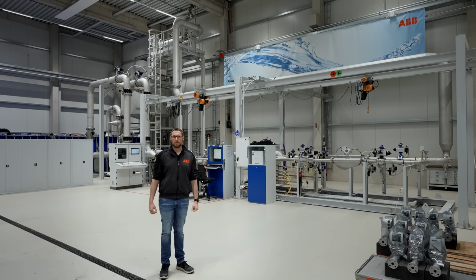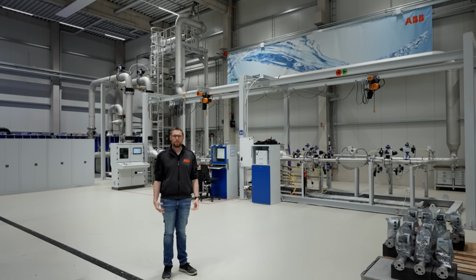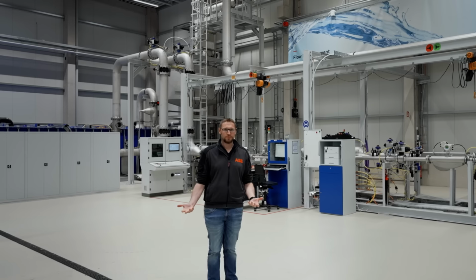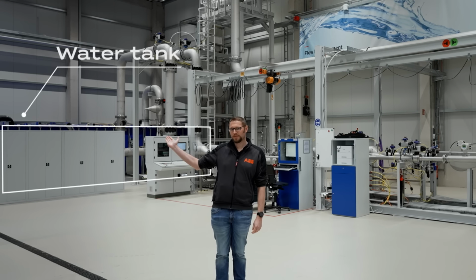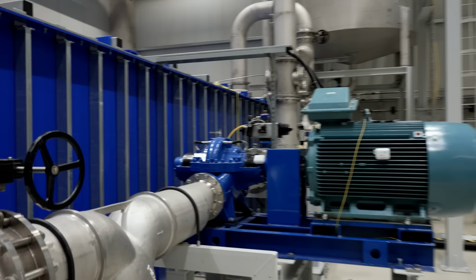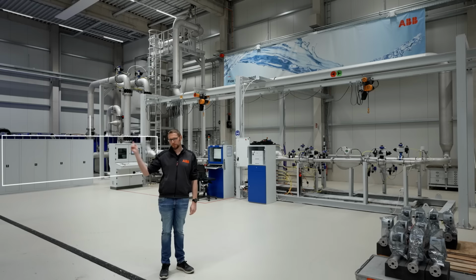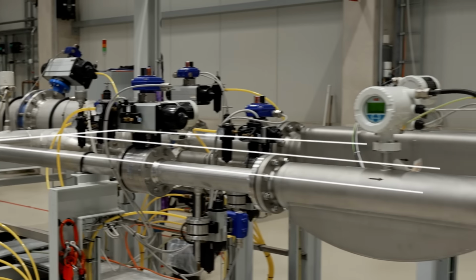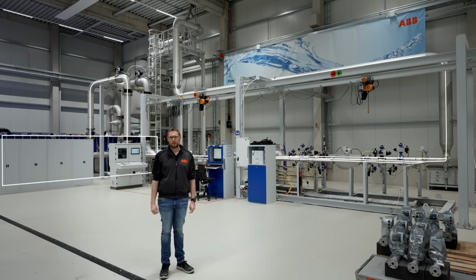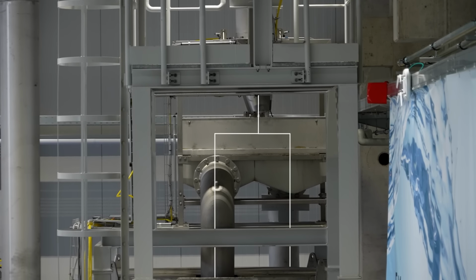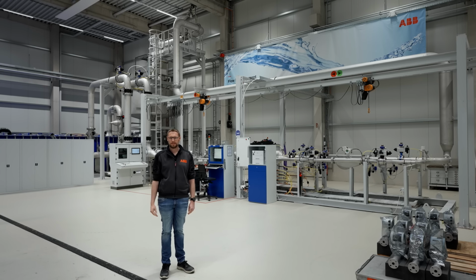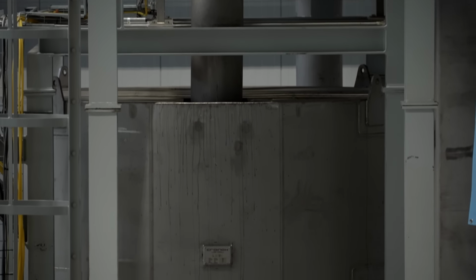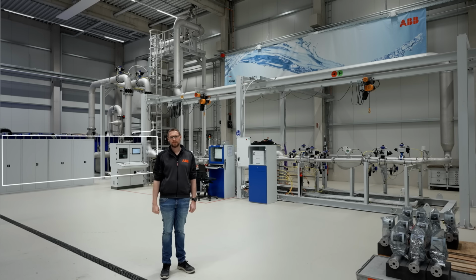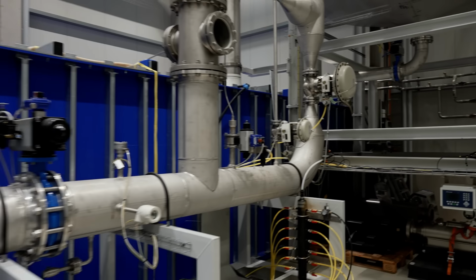So, for our calibration, we basically pump water in a circle and compare the flow rate of the meter under test with a reference. So how do we do it? At my right side, you see this big blue water tank with 150,000 liters of water. From there, we pump the water through the pipes to the meter under test, further through the master meter, then further on top of the rig to the diverter, and there we decide if there is a master meter calibration for the standard accuracies. The water goes back directly to the tank, or if we have high accuracies, then the diverter puts the water directly in the big weigh scale tank and we're weighing the water. And after the calibration, the water flows back to the water tank. Now let's have a closer look at it.